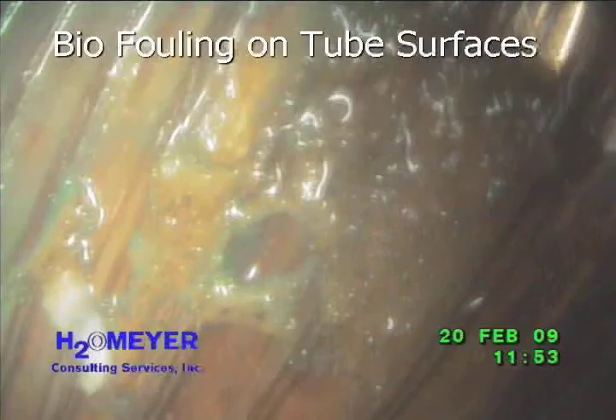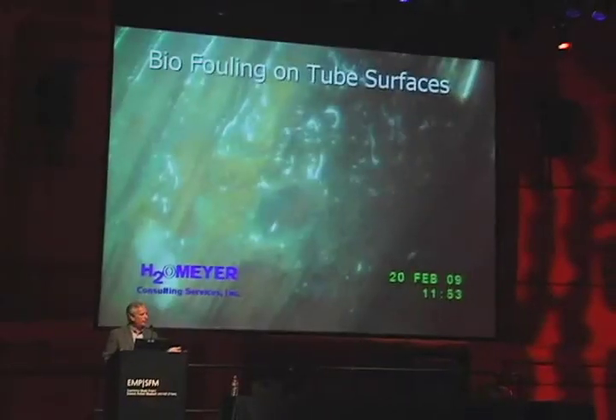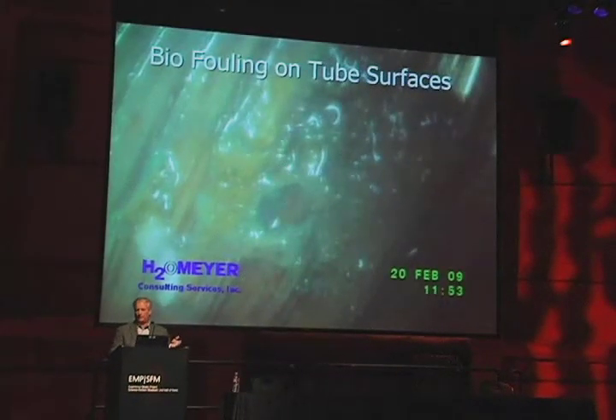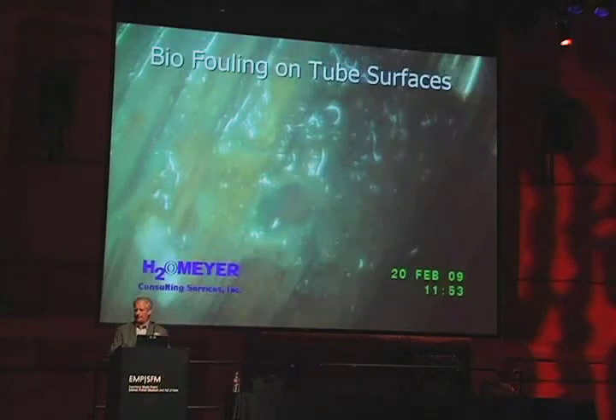The nice thing about the borescopes is we can actually take perpendicular angular shots of the tubes themselves. Here's an example of a tube that's got biological fouling. You can see the enhancements right here, and you can see the biological material, like a gelatinous material, in between these things. That actually acts as an insulator to the tubes as well, and also causes biologically influenced corrosion. In other words, bacteria, in its metabolic process, secretes acids. So right there on the pipe surface, you're going to have acids secreted, and that could cause damage to the tubes.